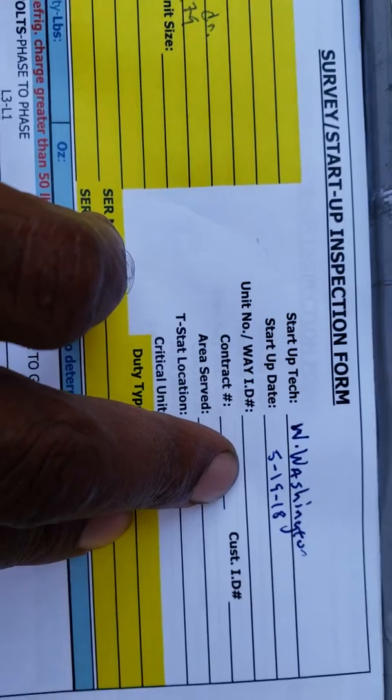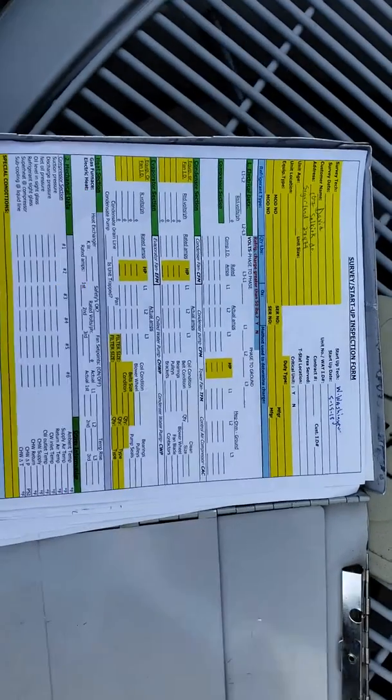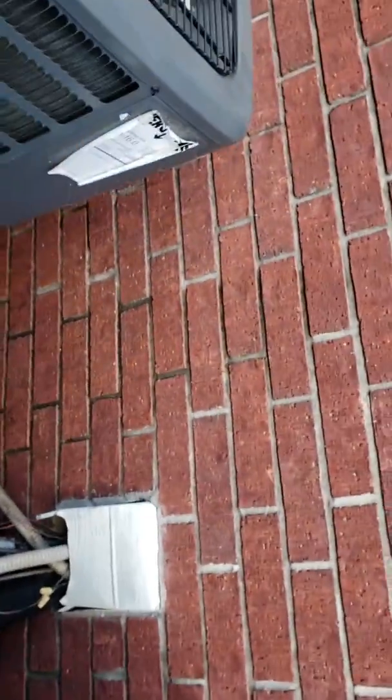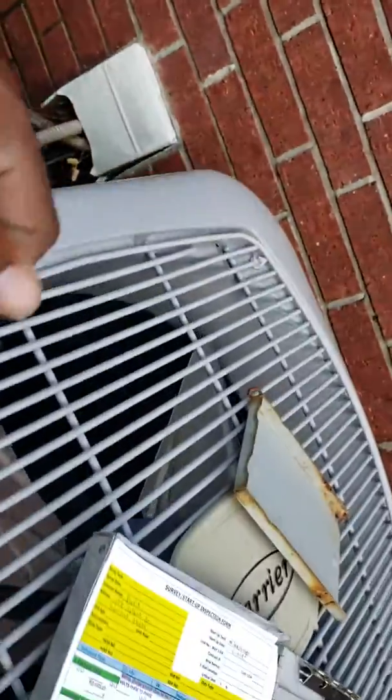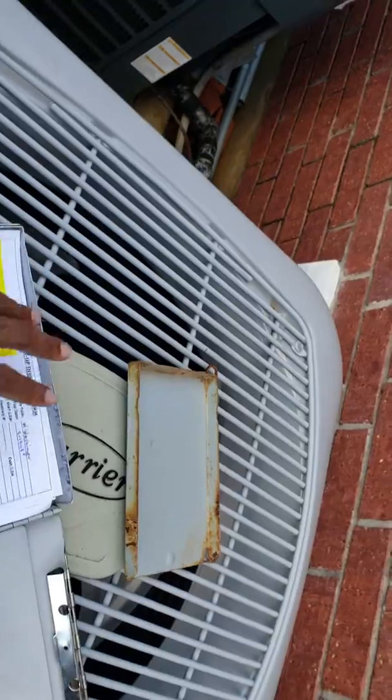I've got today's date on there — 5-15 — so just say if there's a pressure loss and he calls me back, or next year around that time he calls me back to do a maintenance, if there's a significant difference in the pressures or anything, I have all that documented. I'm going to send him an email of everything that I find. I'm going to hook my gauges up — all I'm going to do is take a picture of the pressures, take a picture of the motor amps and the fan from my gauges and just snap a quick picture, and I'm going to sit down at night and record everything that I got.